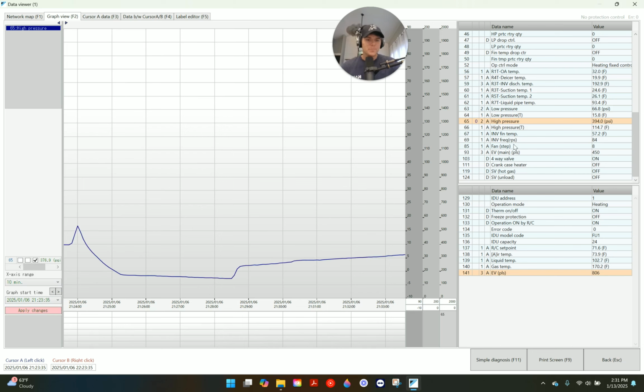Next item. Let's move over to the other thing that we need to understand, which is the three things that I talk about, right? Suction superheat, discharge superheat, subcooling. Now we know this particular issue is a high discharge or high pressure in the system. Sensors have already been checked. All the basic stuff has been checked. Remember, it's a 2-year-old unit. So there's not a whole lot that could go wrong there, but there also could.